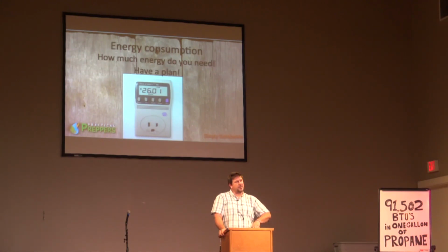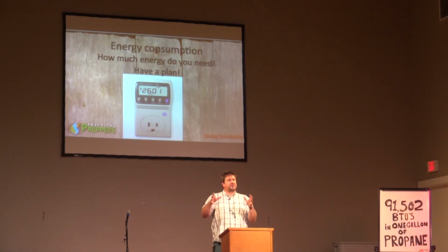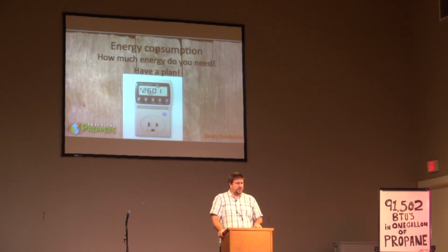It can cut startup load down to about half, I don't think it goes lower than that. It's made for things like a compressor - if I wanted to run my 5 horsepower shop compressor off my inverter, I can't; my inverter won't start it right now. But with the IntelliStart on it, it'll drop the startup draw. Search YouTube for IntelliStart and it'll show you graphs of how it lowers the power needed to start your device, so you can run it off a smaller generator or off solar.